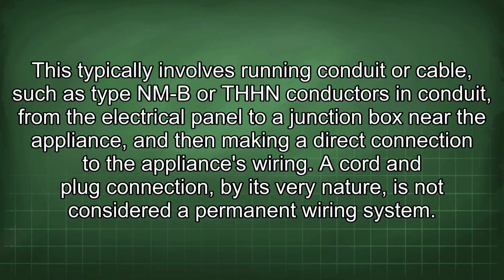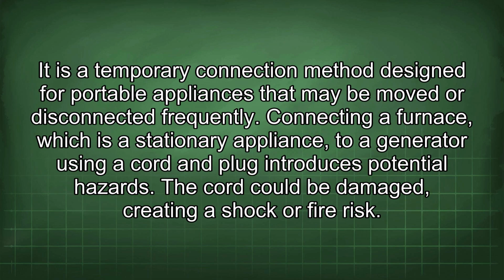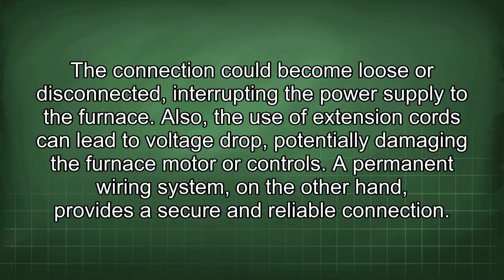A cord and plug connection, by its very nature, is not considered a permanent wiring system. It is a temporary connection method designed for portable appliances that may be moved or disconnected frequently. Connecting a furnace, which is a stationary appliance, to a generator using a cord and plug introduces potential hazards. The cord could be damaged, creating a shock or fire risk. A connection could become loose or disconnected, interrupting the power supply to the furnace. Also, the use of extension cords can lead to voltage drop, potentially damaging the furnace motor or controls.